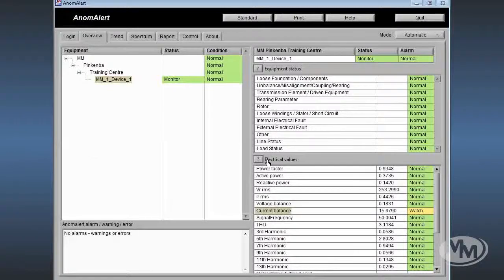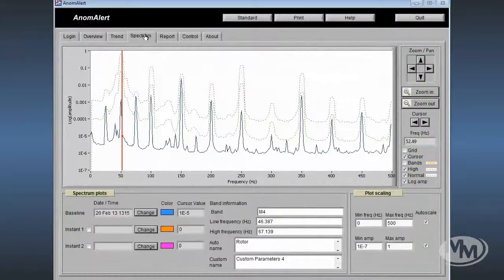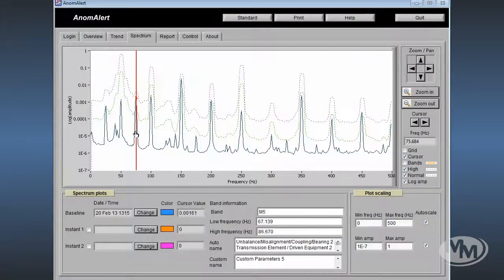The spectrum page of the Anomalert software shows the PSD plot or power spectrum density. It is from this plot that mechanical faults are determined and derived. The various frequency bands are usually indicative of different mechanical problems. For example, the one under the cursor at the moment usually indicates issues with unbalance, misalignment, coupling or bearings.